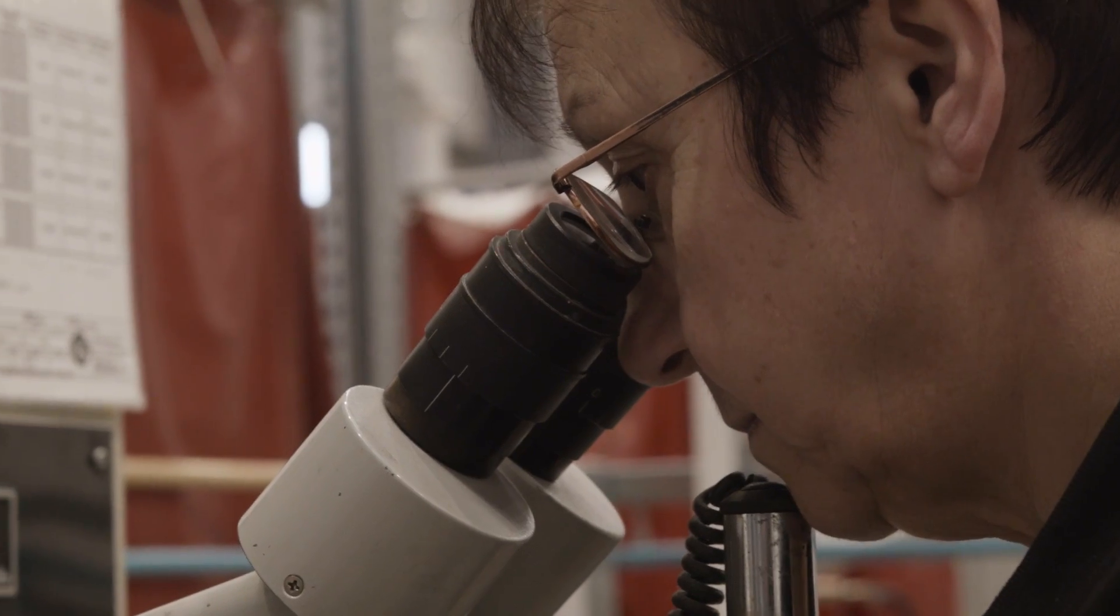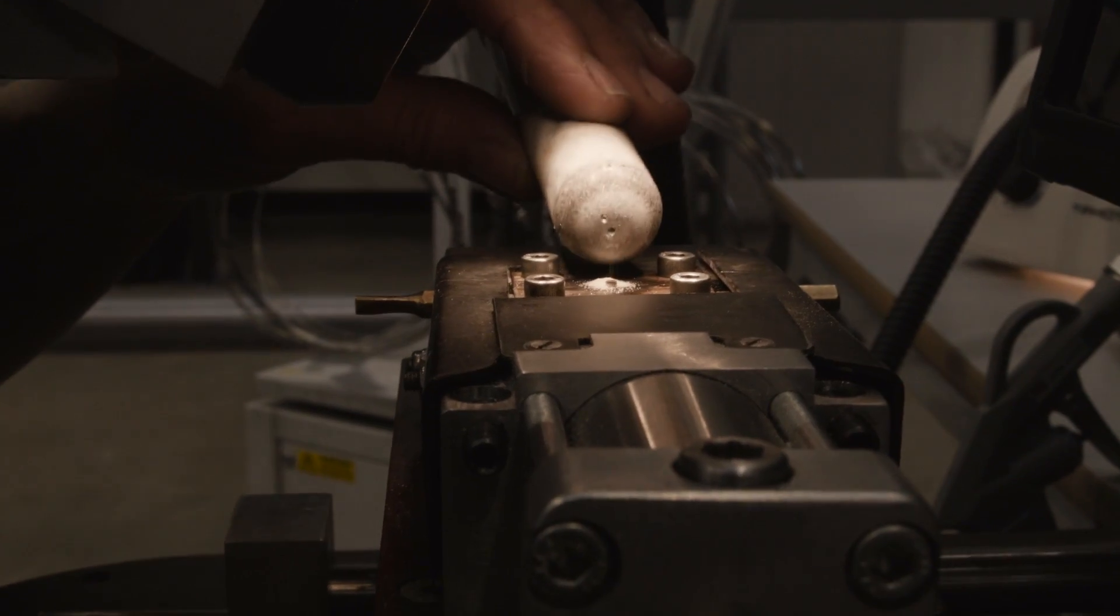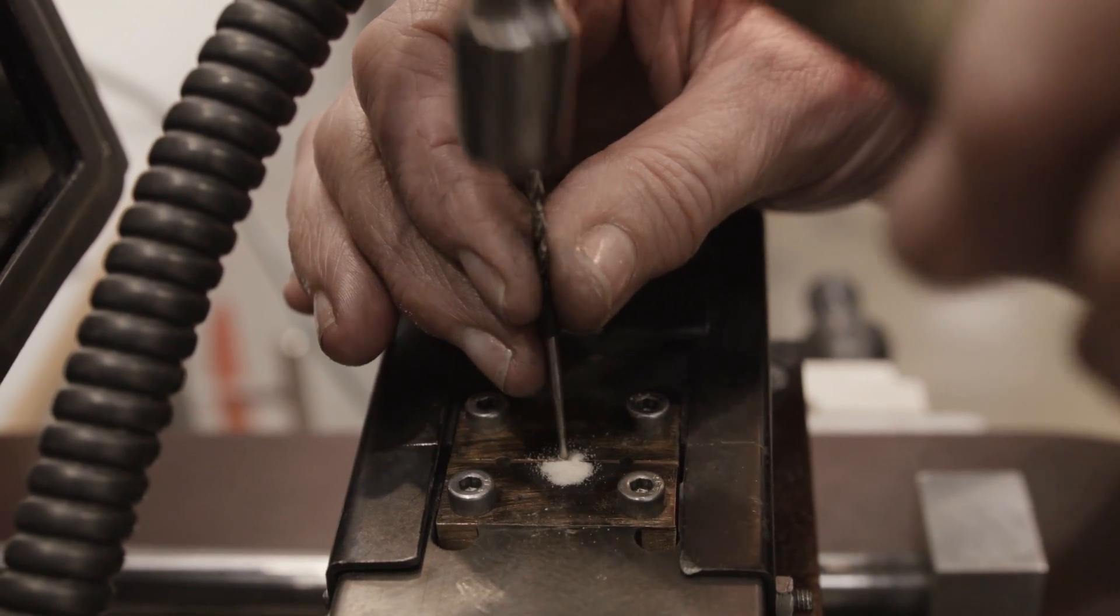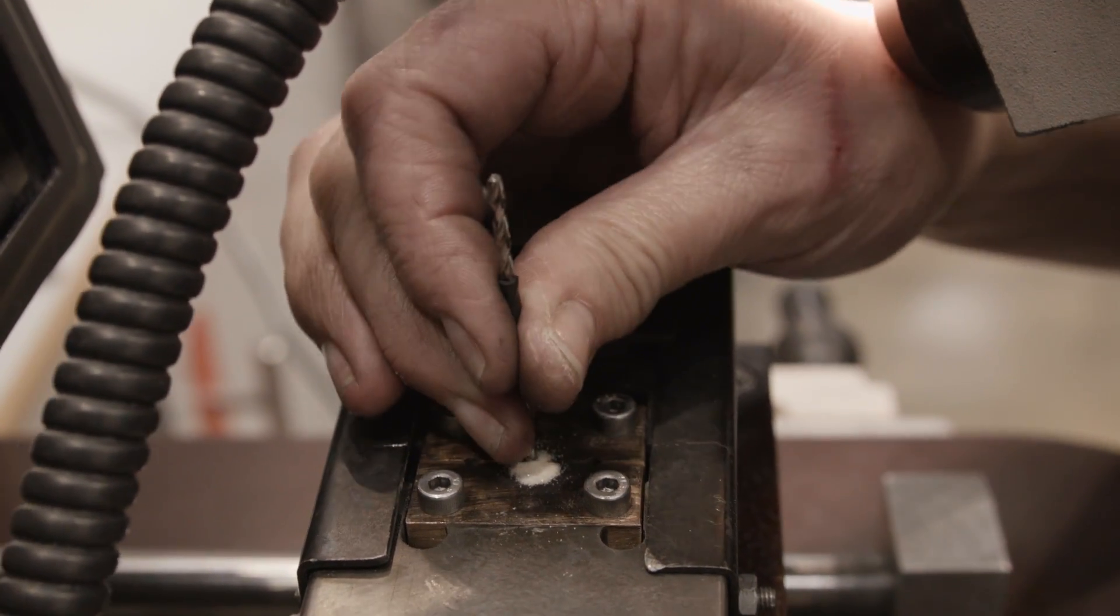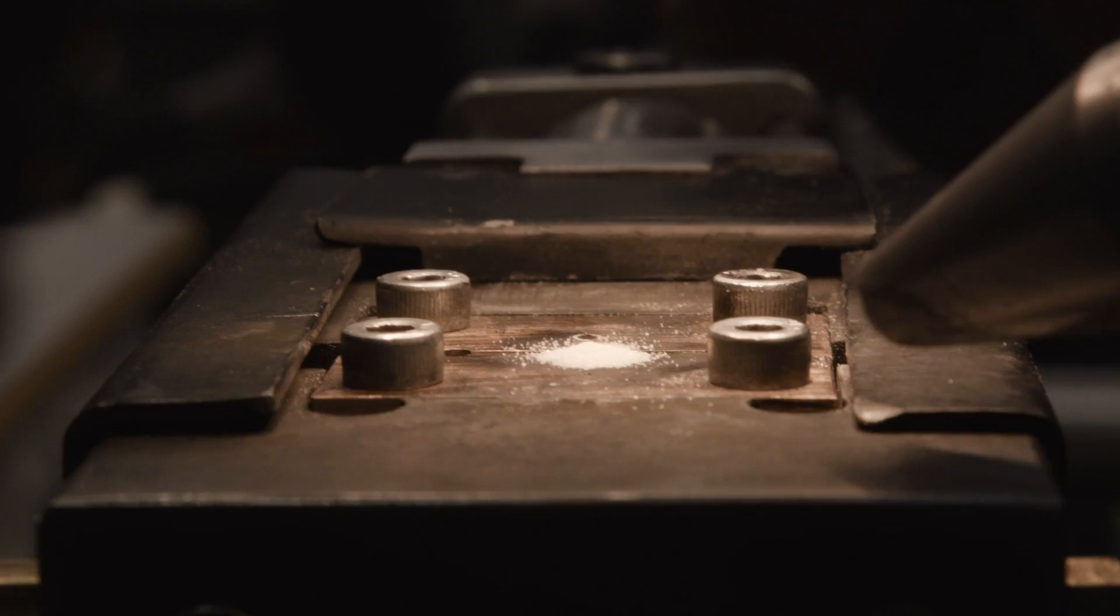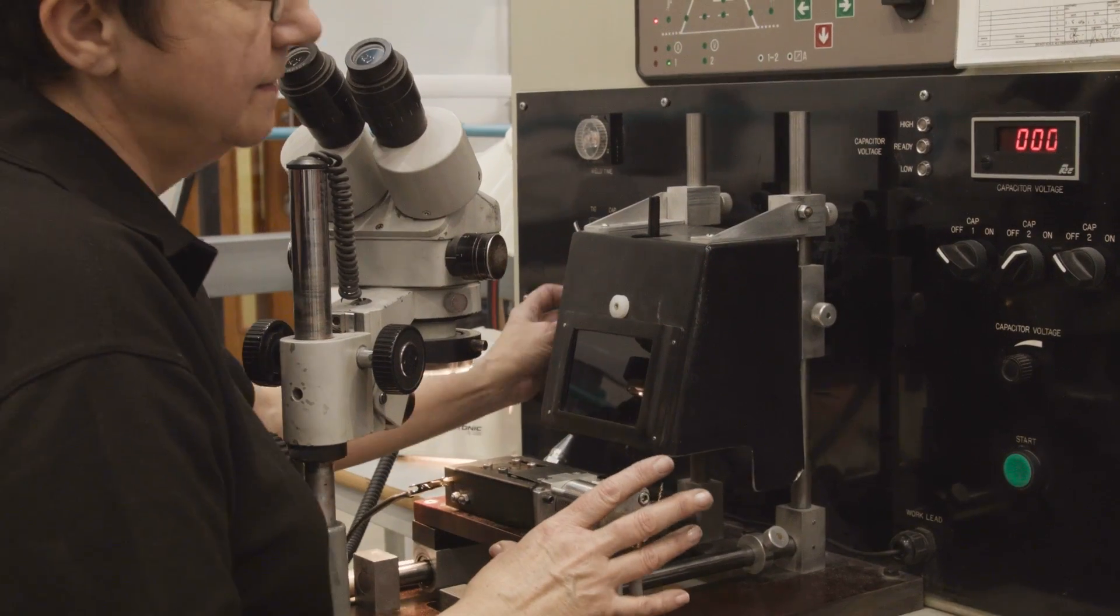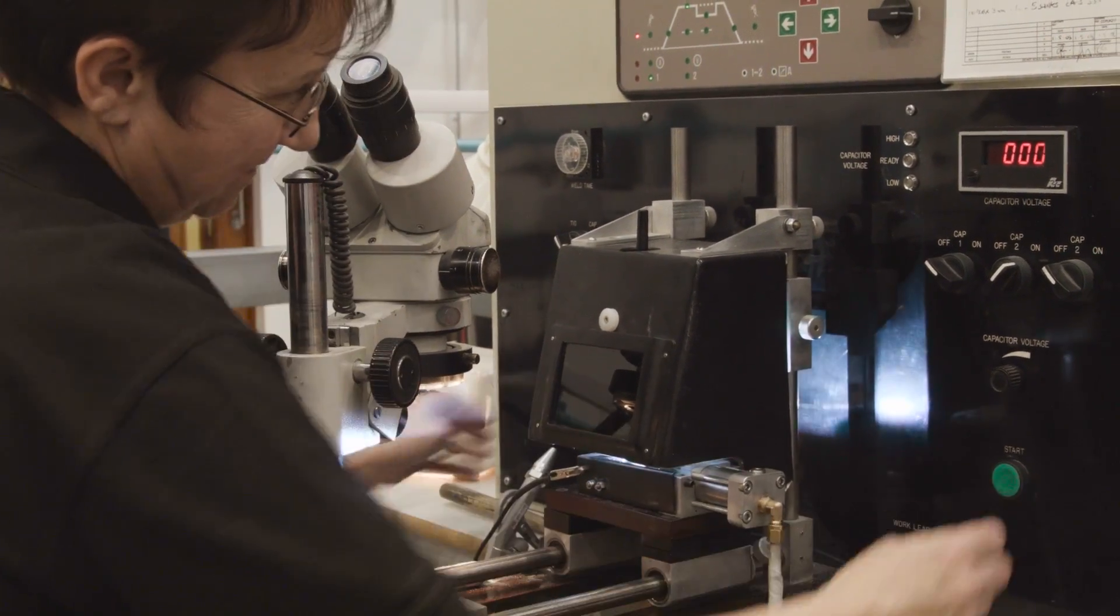The hot junction is then prepared for sheath closure. Clean heated magnesium oxide powder is poured into the cable and compacted over the thermocouple conductor weld. Again the sheath closure is finished whilst under an argon atmosphere.